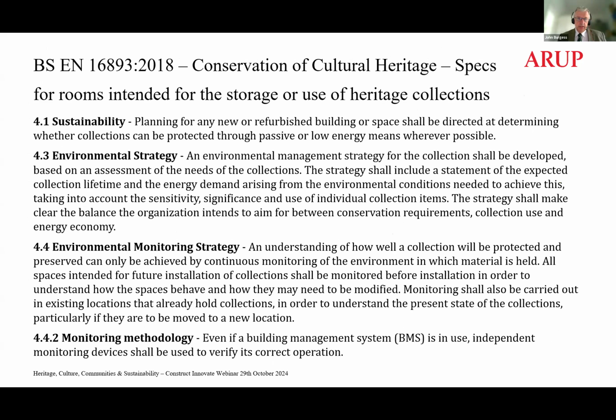Looking at BS 16893, there's a key focus on sustainability, asking straight up: can the collections be protected through passive or low energy means? On the Crawford Art Gallery, I'll speak about two examples shortly where, in my career, I've had to change from originally putting in a boiler and chiller system to achieve heating, cooling, and dehumidification, to one where maybe we could disband with them altogether.